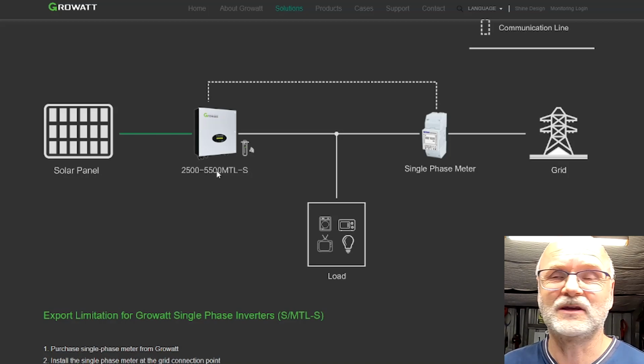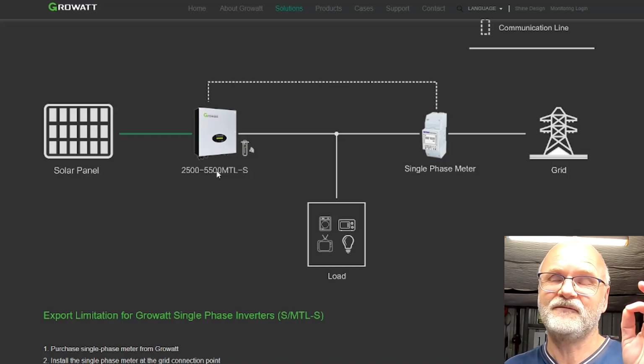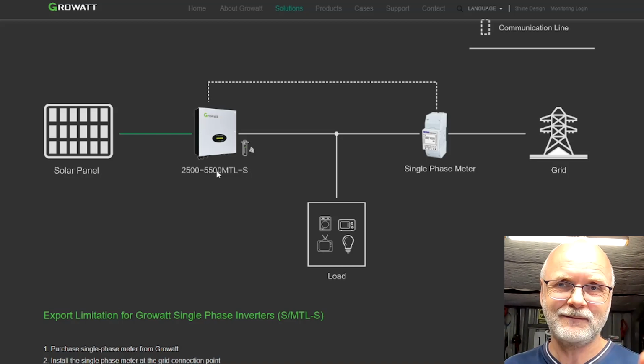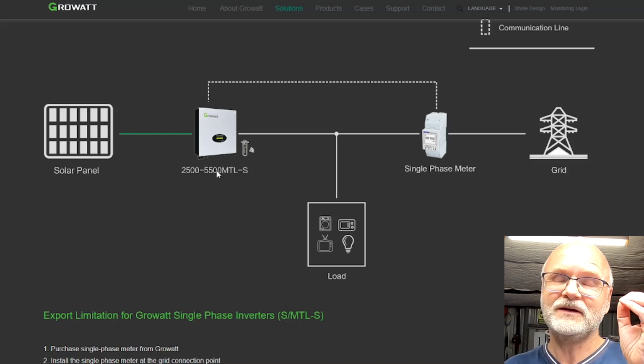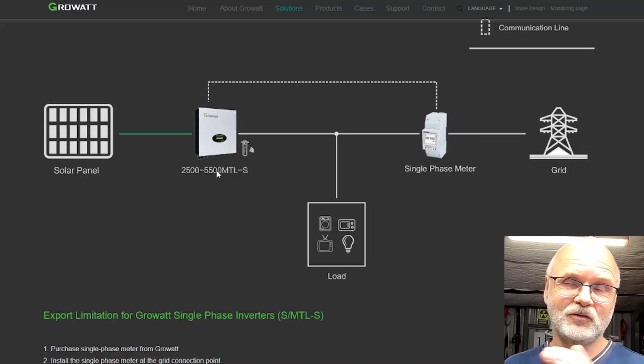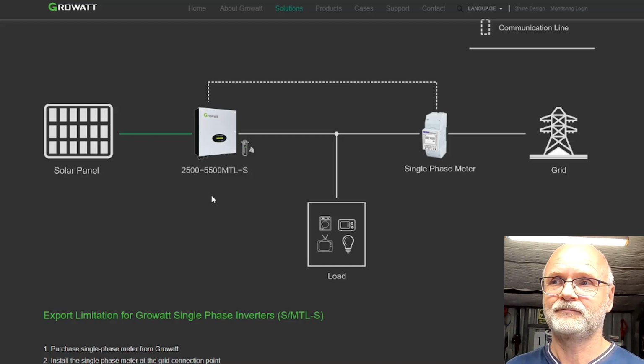But can you see a battery in here? No. This is an AC coupled inverter. This works only during the day. This is for situations where you have a limit to export, or even a zero limit to export - you are not allowed to export anything.